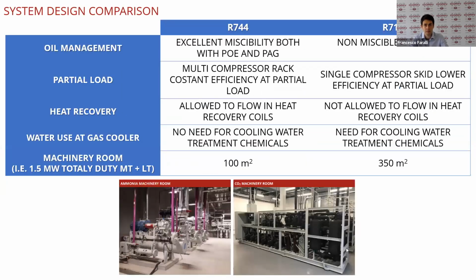And here is a system design comparison, generally speaking, on the installation. If we compare ammonia and CO2 for industrial application, we have oil management that is easier for CO2, which can work with POE and PAG thanks to the excellent miscibility with these oils. At partial load, since we have a rack made of several compressors, the efficiency is more or less constant, instead of having a system with a single compressor working at partial load.